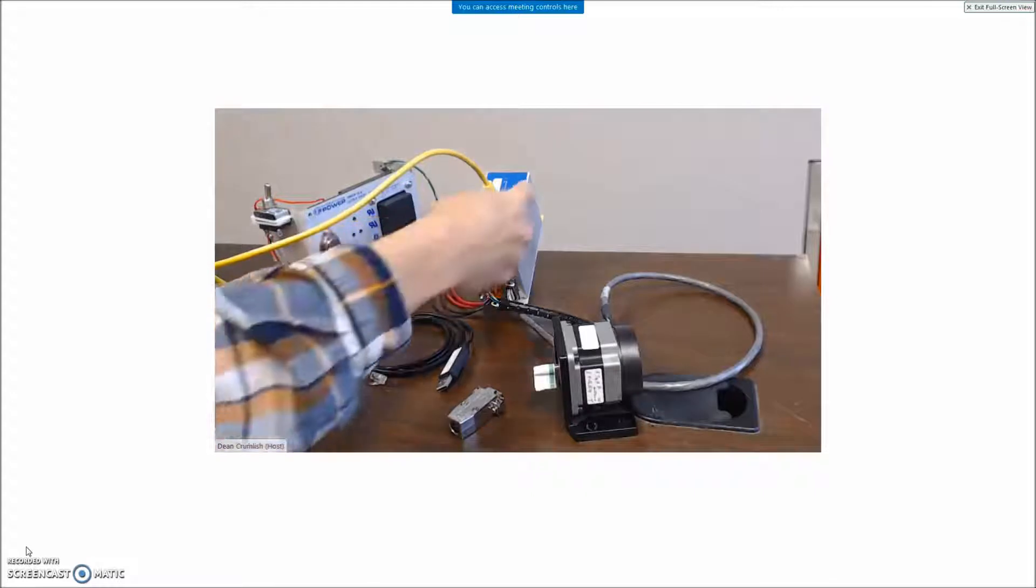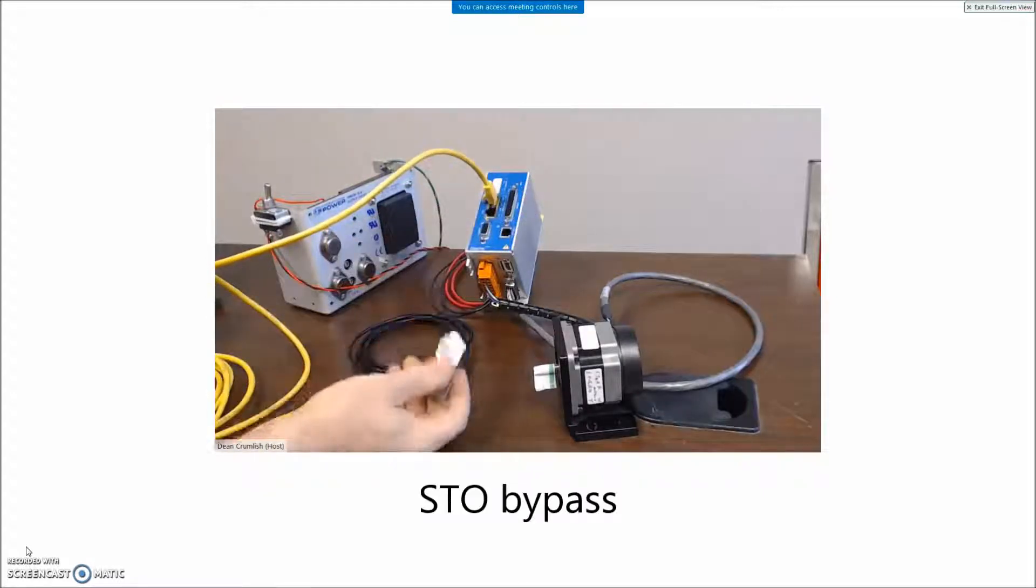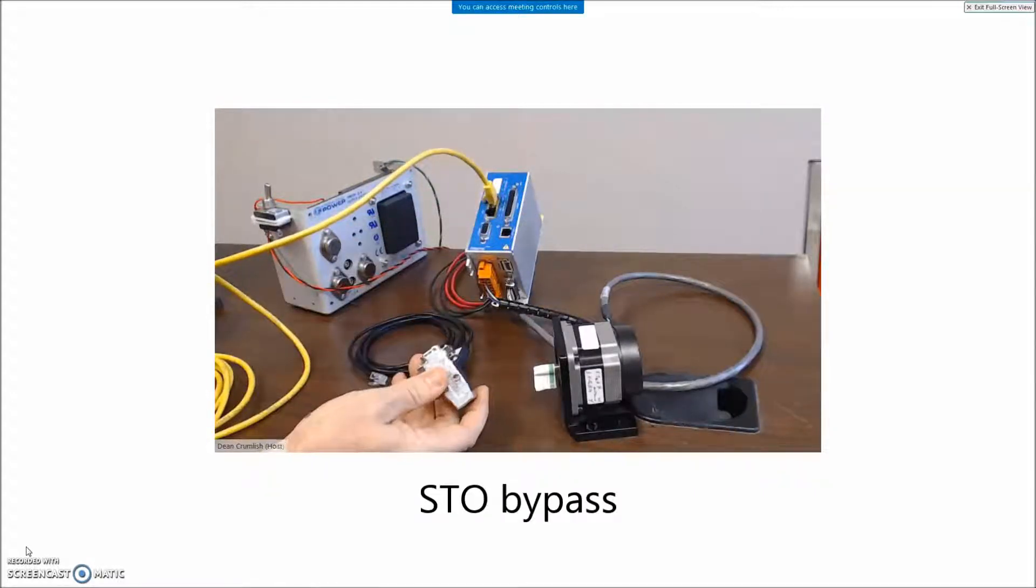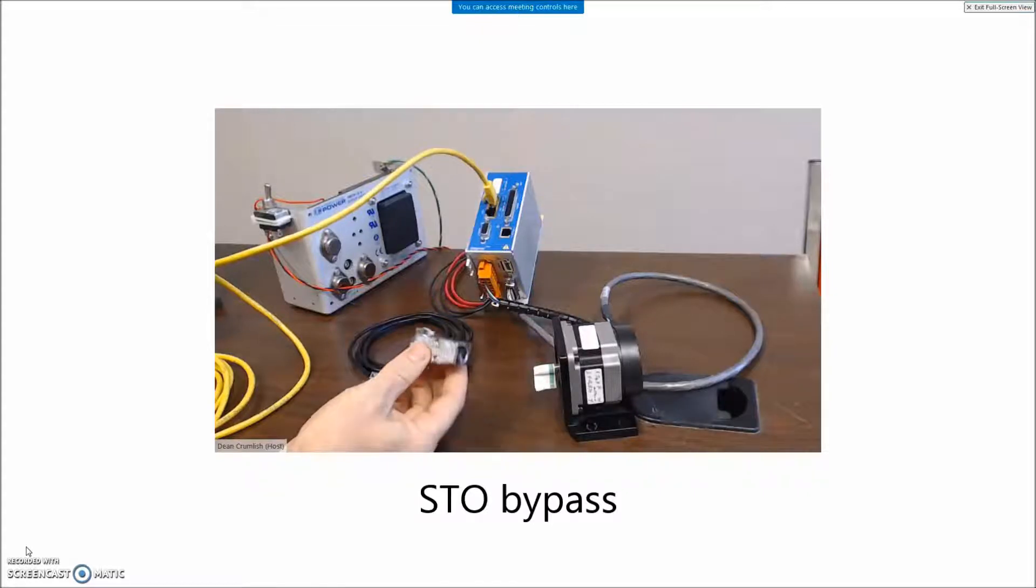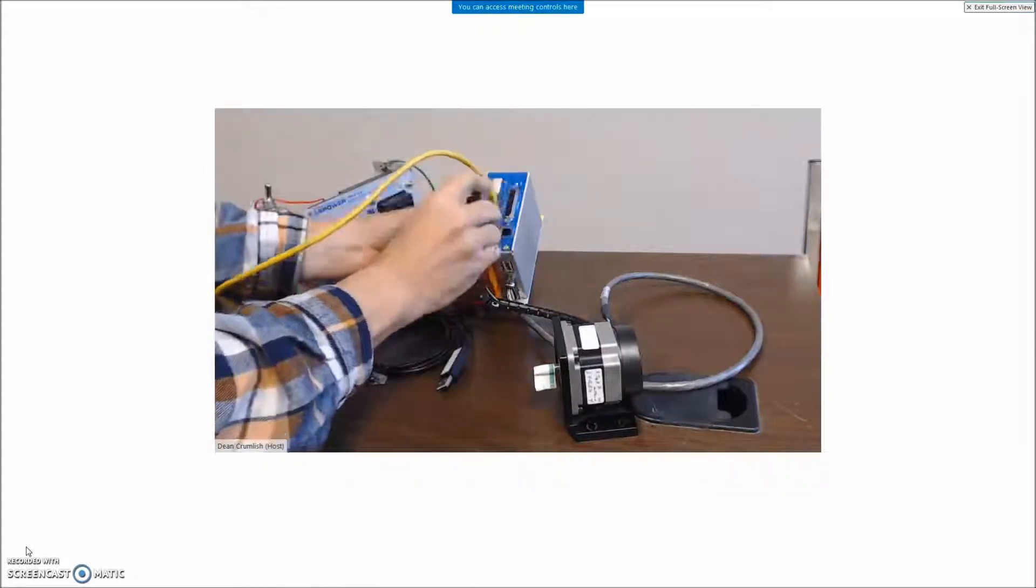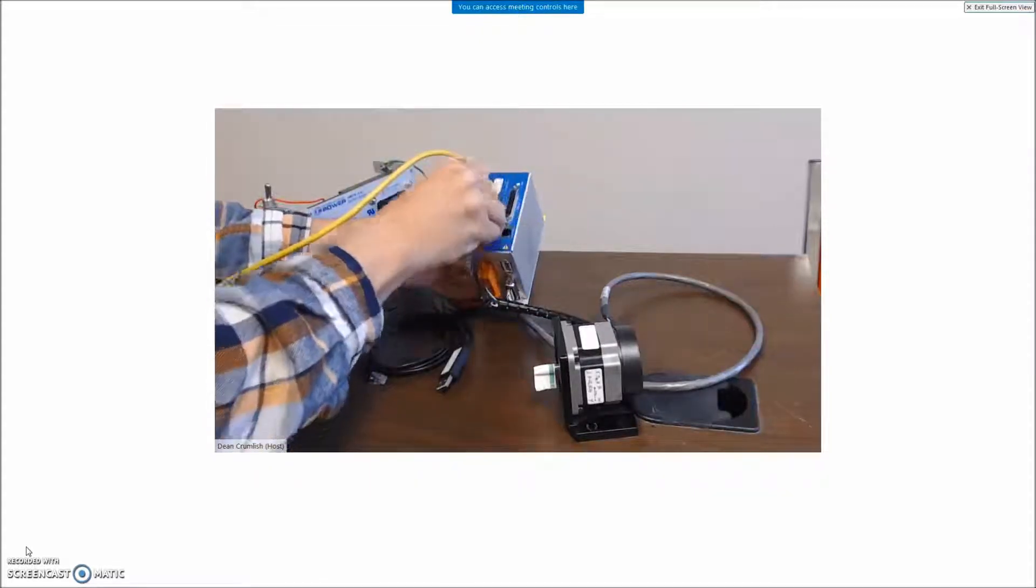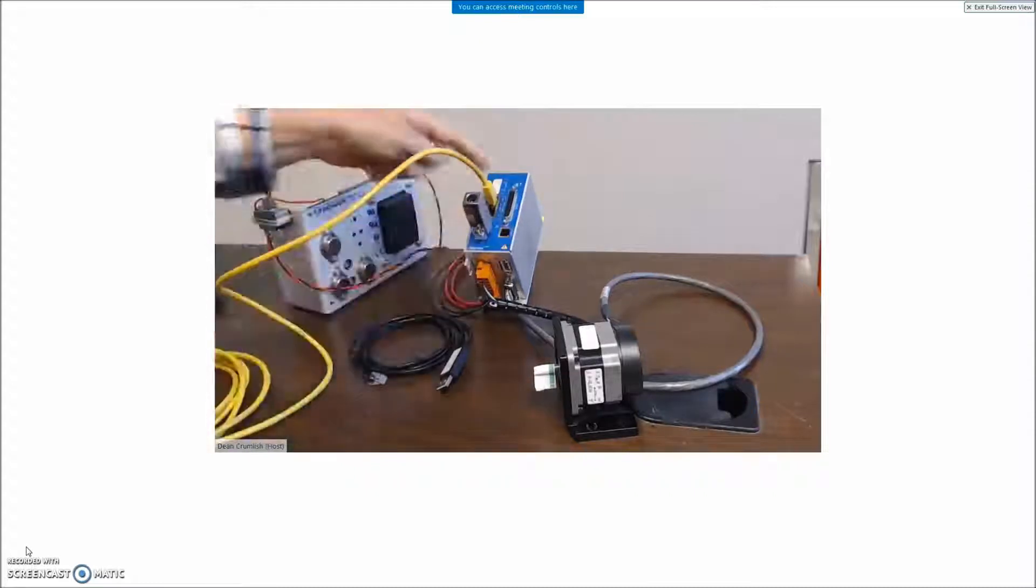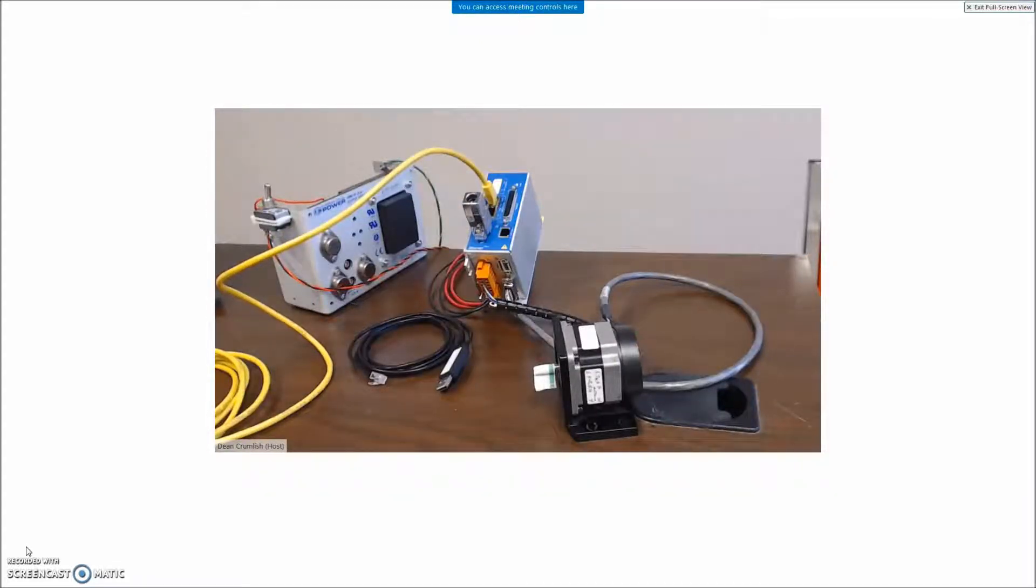I've got a fast blinking light because of my STO. I have to bypass the safety so I'm going to use the STO jumper. This will put the drive into a disabled mode waiting for the EtherCAT master to come along and enable it.